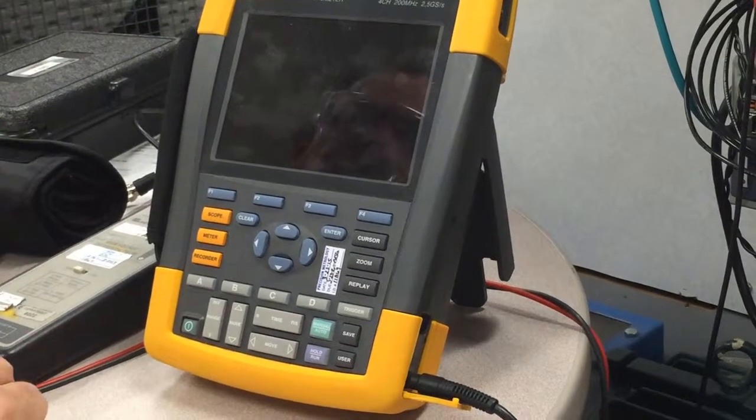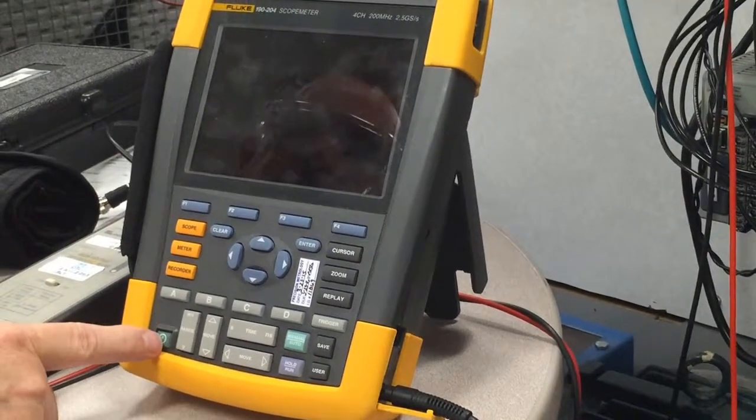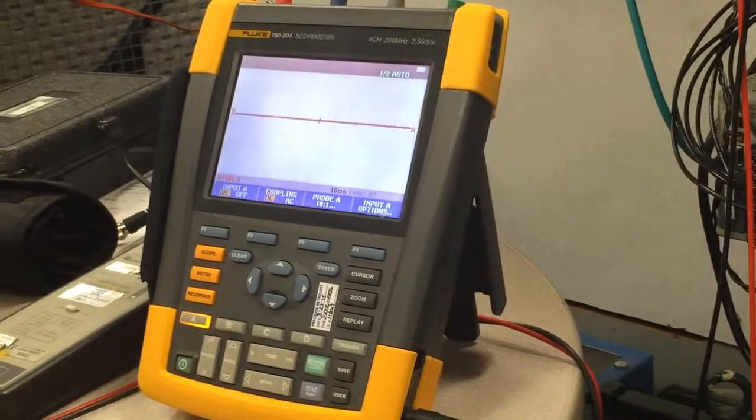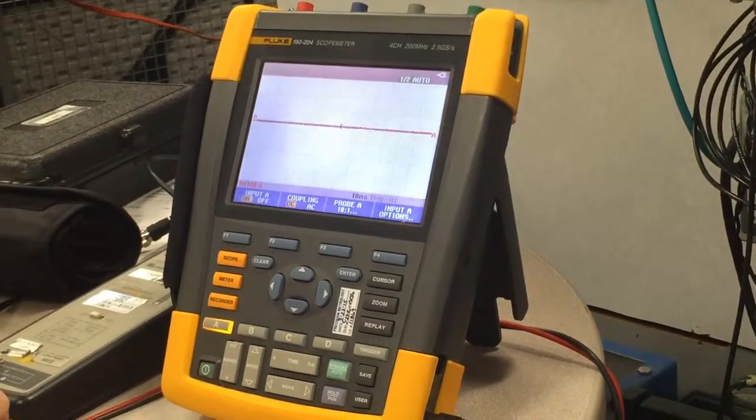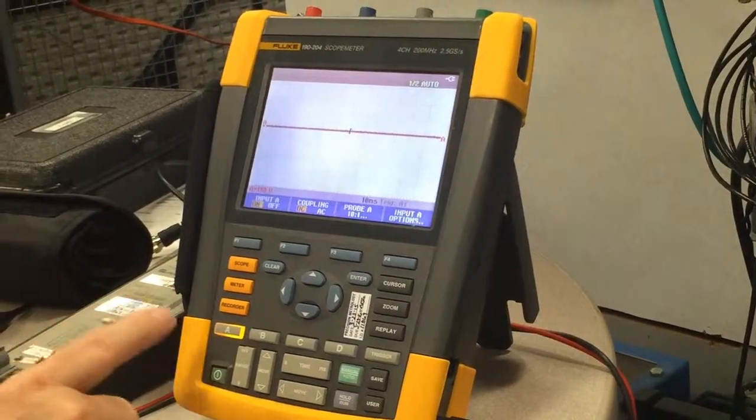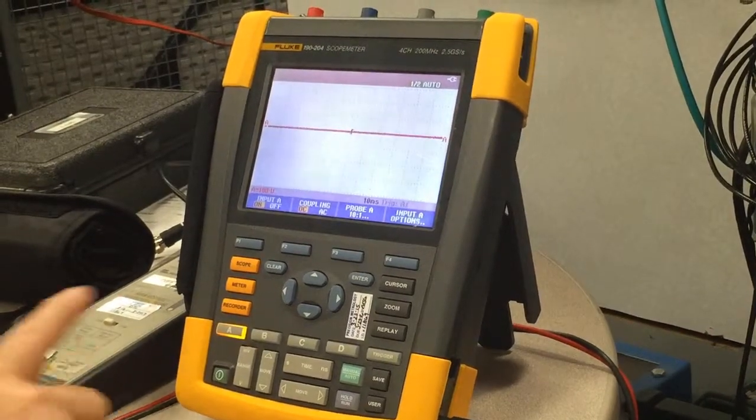In this demo, we're going to be connecting to the output of a VFD. So the first thing you want to do, of course, is turn on the scope meter. And then what I like to do, because you never know how the scope meter was set up before, is I like to reset to factory defaults.